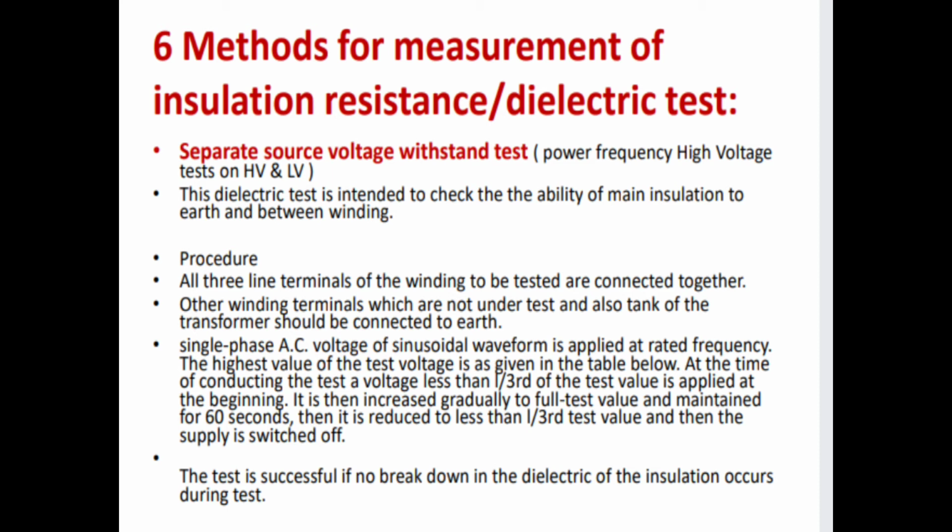All three line terminals of the winding to be tested are connected together. Other winding terminals which are not under test, and also the tank of the transformer, should be connected to earth. Single phase AC voltage of sinusoidal waveform is applied at rated frequency. The highest value of the test voltage is given in the table below.